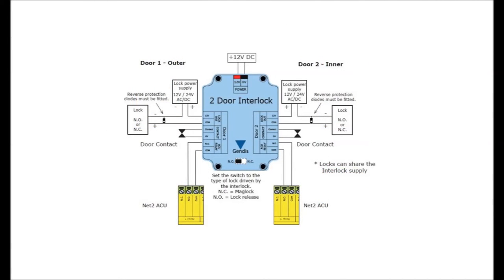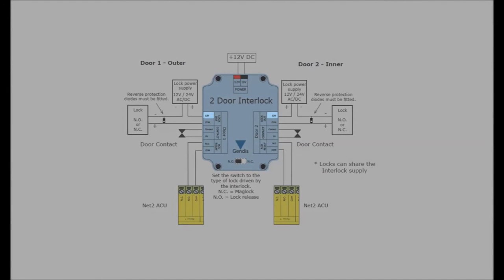Taking a closer look at the interlock again, we can see how the device is laid out. On both door 1 and door 2, it is worth noting that the 12V label refers to the connection of 12V or 24V from the lock, rather than there actually being 12V present at that location.